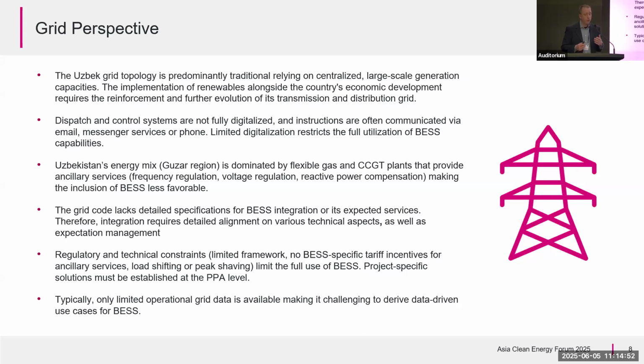Particularly in this project, we have a flexible gas and CCGT plant which is able to provide frequency regulation, as well as voltage regulation and reactive power provision. As a result, it makes the inclusion of the BESS less favorable. Technically, the grid code also lacks specification on how BESS shall be integrated. So we see both regulatory and technical constraints, and the technical setup of the grid is limiting the use cases for the BESS.